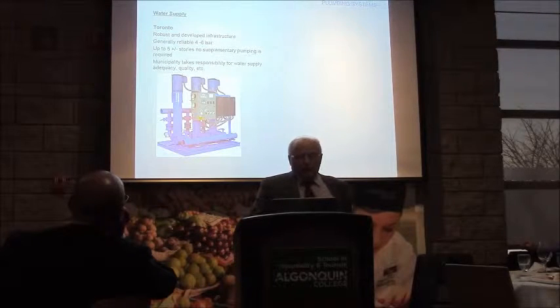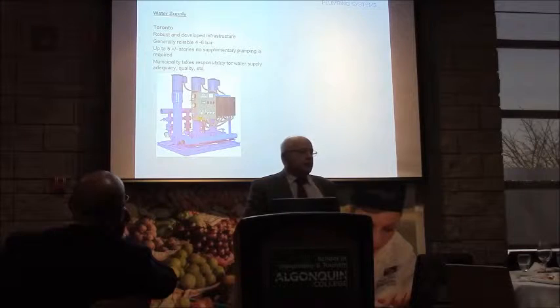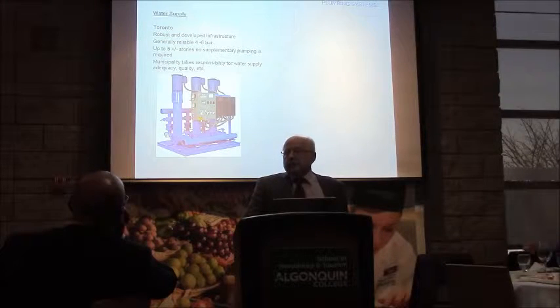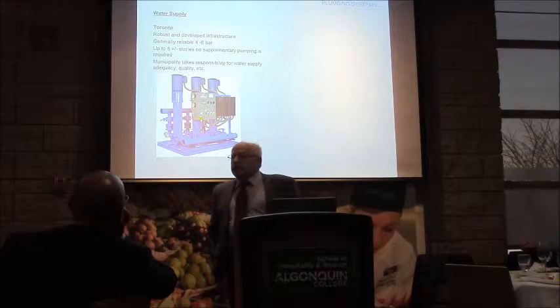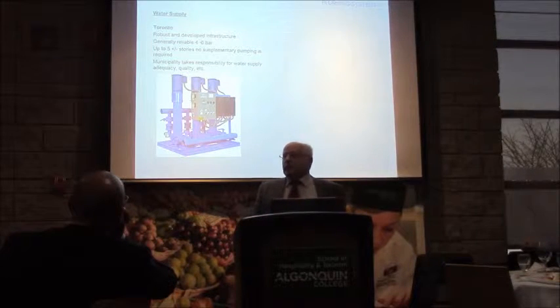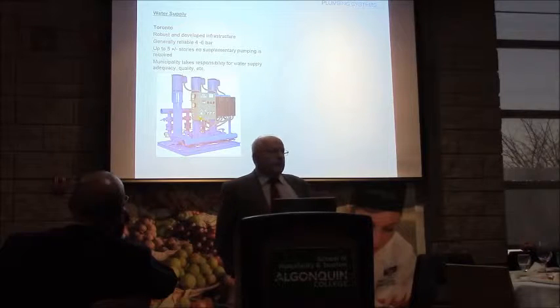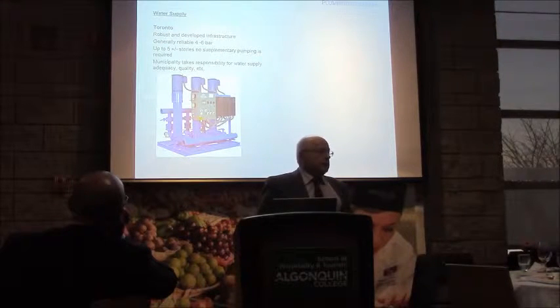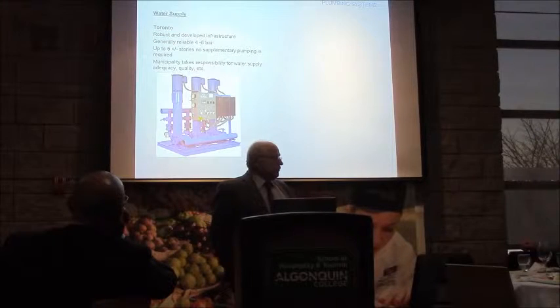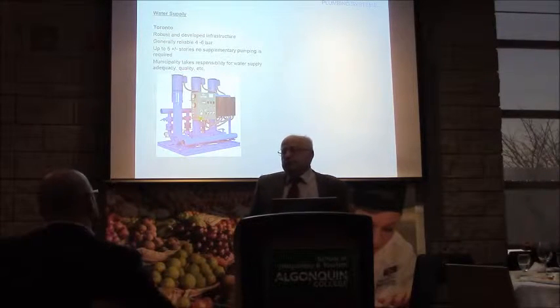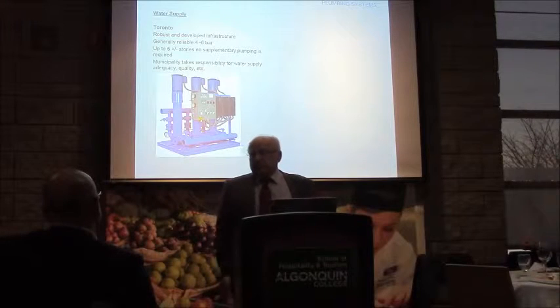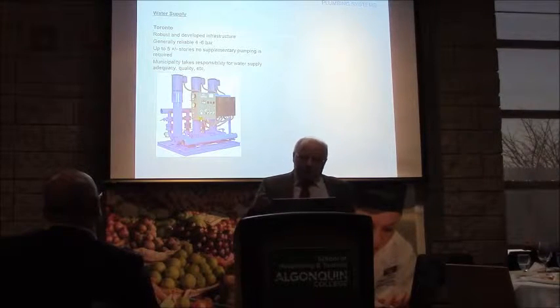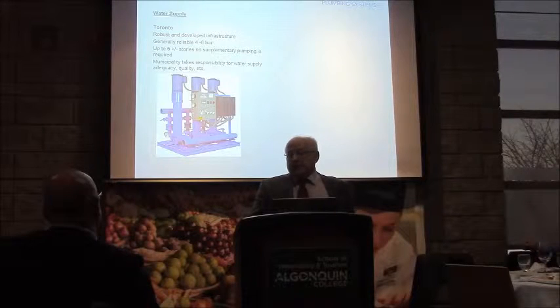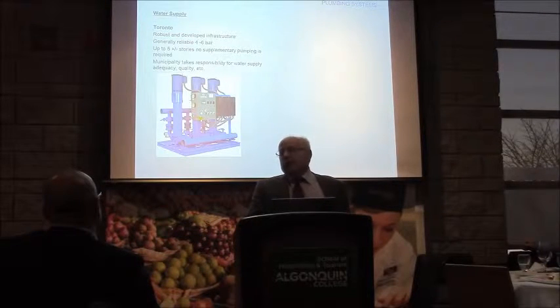In Toronto, of course, we're quite different - we rely on our municipal services. Nonetheless, in a tall building we'd have to store fire water at the highest level. In Toronto, that was a mandate because the fire chief was stomping his feet about it for many years, and he had the final say. He literally had projects redrawn when it was topped off structurally if it didn't have a supply at the top of the building. Even though it wasn't necessarily mandated by code at the time, he was the authority having jurisdiction, so there.